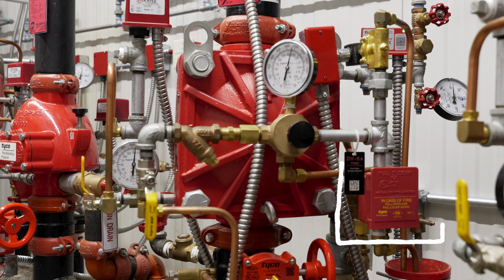Other components on the valve trim assembly include a manual release and pressure alarm switch. Operating the manual release will override the entire releasing mechanism and open the valve. This function, of course, is reserved for emergency situations and should be used if there is indeed a fire and the normal releasing system has failed, or if a fire is confirmed and the releasing system simply hasn't operated yet. The manual release is entirely mechanical and will work regardless of building or releasing panel power failure.